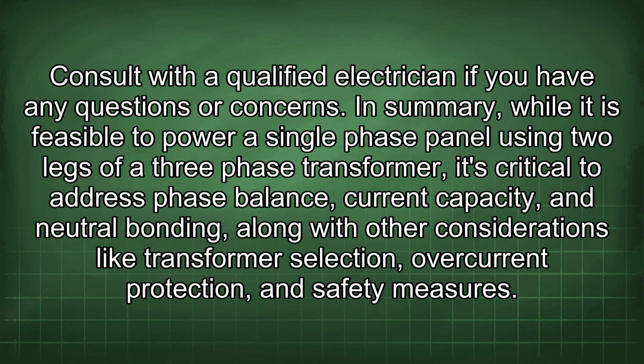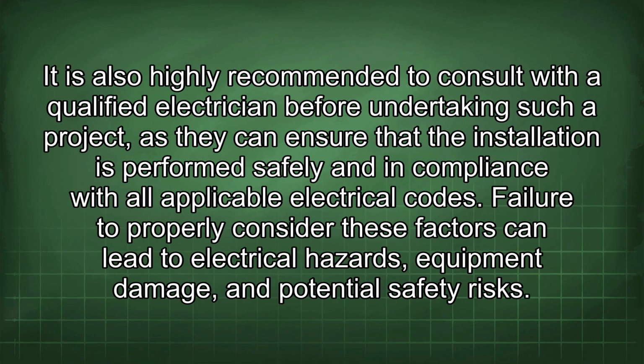In summary, while it is feasible to power a single-phase panel using two legs of a three-phase transformer, it's critical to address phase balance, current capacity, and neutral bonding, along with other considerations like transformer selection, overcurrent protection, and safety measures. It is also highly recommended to consult with a qualified electrician before undertaking such a project, as they can ensure that the installation is performed safely and in compliance with all applicable electrical codes. Failure to properly consider these factors can lead to electrical hazards, equipment damage, and potential safety risks.